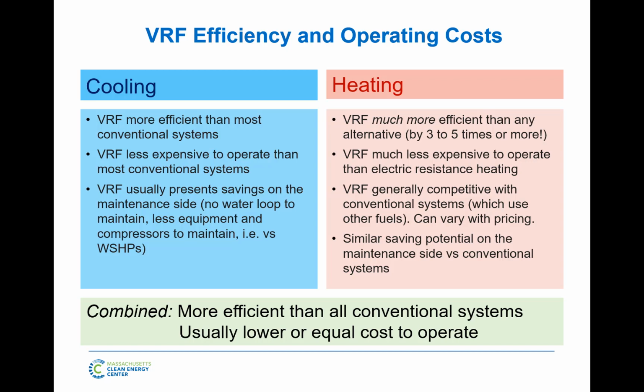But in general, the biggest reason for the efficiency of these systems is the inverter-driven compressor, the variable speed compressor. Both technologies are using that same compressor technology. So VRF and mini splits are both using variable speed compressor technology. And although the commercial equipment might be more bells and whistles, more efficient itself, installation plays a massive role in how efficient the system is going to be. Are we comparing a central VRF system with 300 feet of piping between the outdoor unit and the building itself to a bunch of mini splits that are installed on the patio of every single unit with maybe 15 feet of piping? That can make a difference in your efficiency.